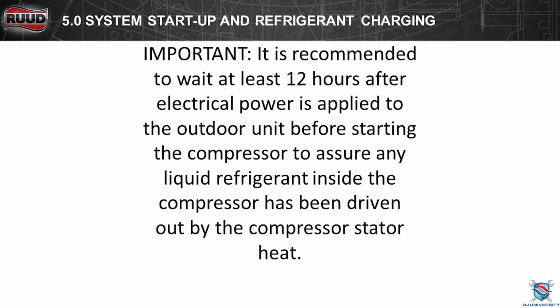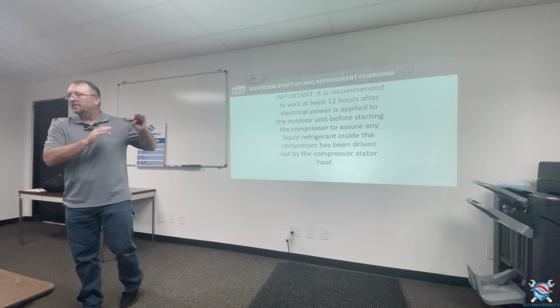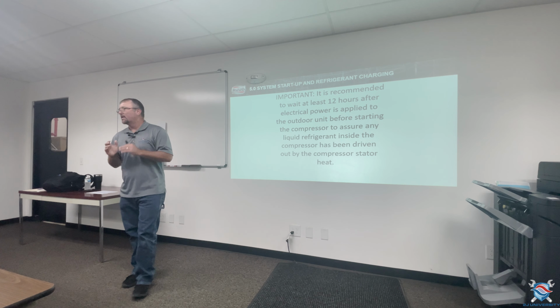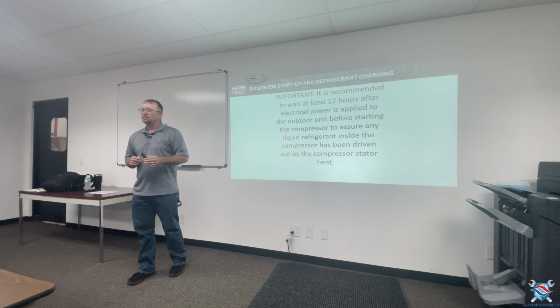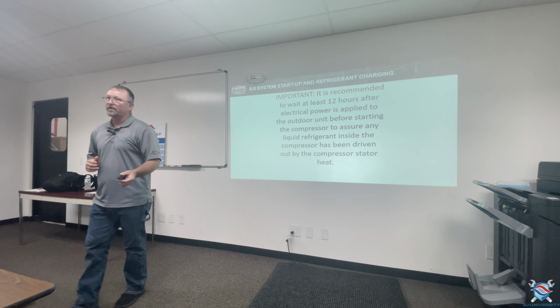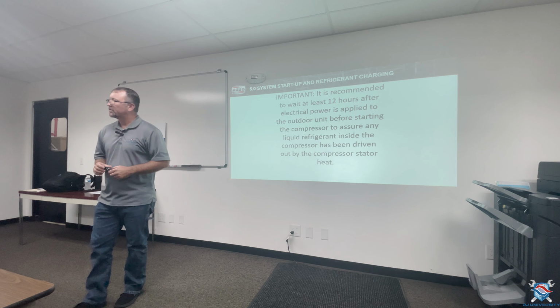I put this in here, and I get a lot of conversation about this. This is right out of the installation manual of an inverter compressor, or an inverter outdoor unit, condensing unit. It is recommended to wait at least 12 hours after electrical power is applied to the outdoor unit before starting the compressor to assure any liquid refrigerant inside the compressor has been driven out by the compressor stator heat. Guys, I'm going to tell you, this is important, but when it's 95 degrees outside, it's probably a little less important than when it's 30 degrees outside, okay, if you're starting up a heat pump.